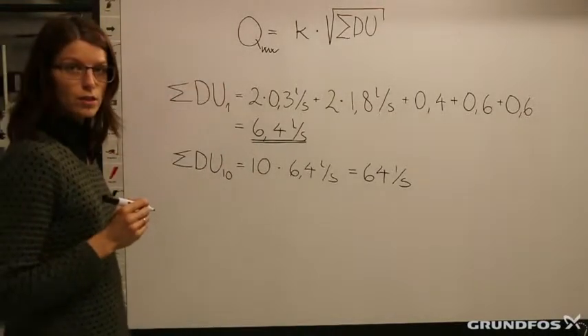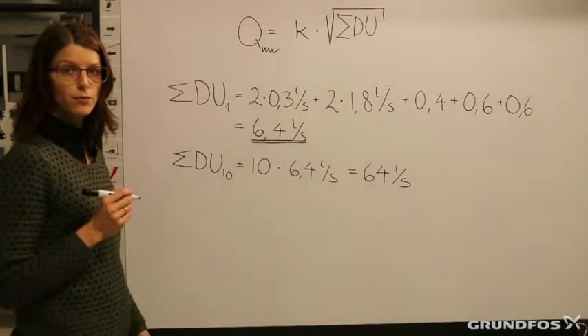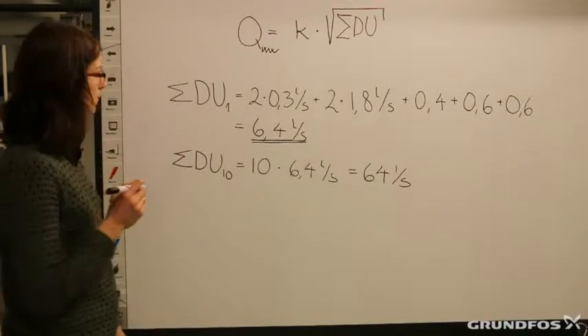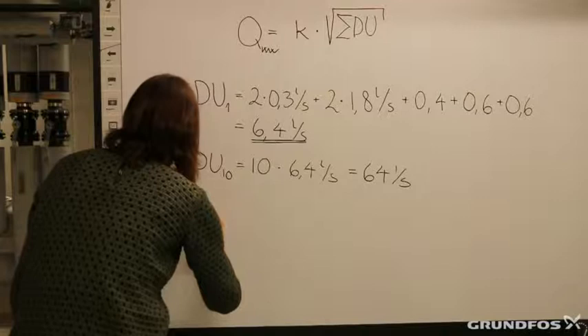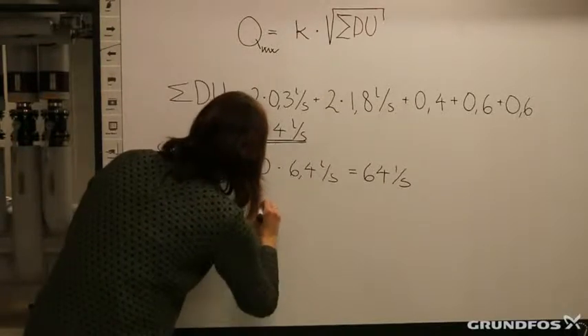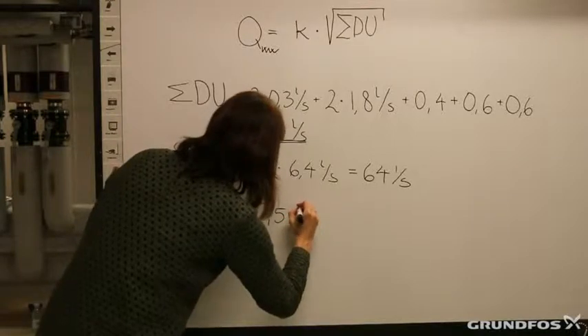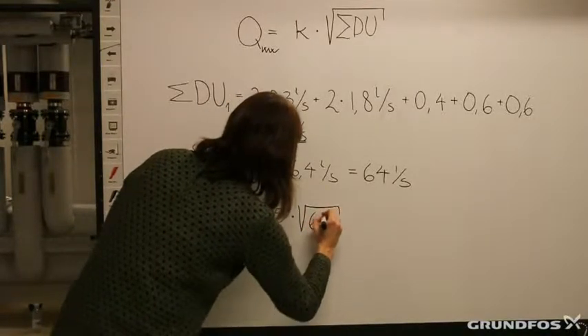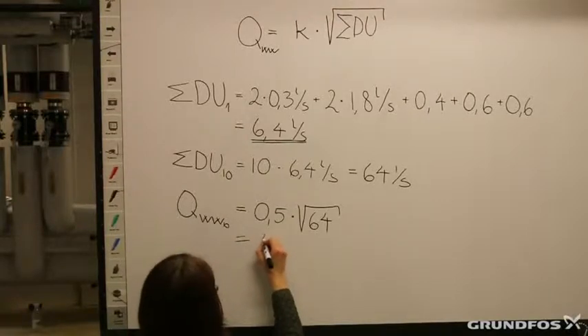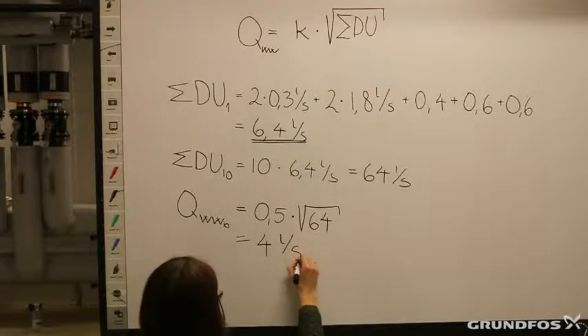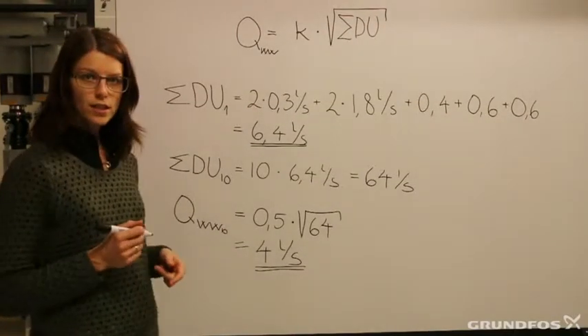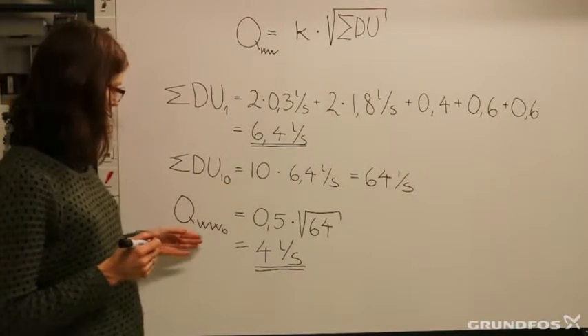Then we need to determine the K factor. As we remember from the table shown just before, we had a K factor for dwellings of 0.5. So we can calculate the wastewater from the 10 dwellings: it will be 0.5 times the square root of 64. This gives us a wastewater flow rate of 4 liters per second from this apartment building.